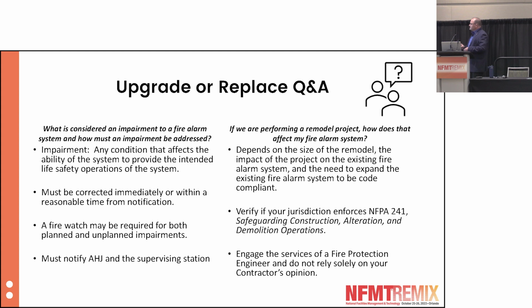The fifth question is, what is considered an impairment to a fire alarm system and how must an impairment be addressed? Well, an impairment to a fire alarm system is any condition that affects the ability of a system to provide the intended life safety of the system. And it differs from a deficiency. So let me give an illustration. If you have a fire alarm system that has 50 smoke detectors in your building, and you test those faithfully every year, and one of those smoke detectors comes up non-responsive or bad, that's a deficiency. One smoke detector, the other 49 are doing their job just fine.